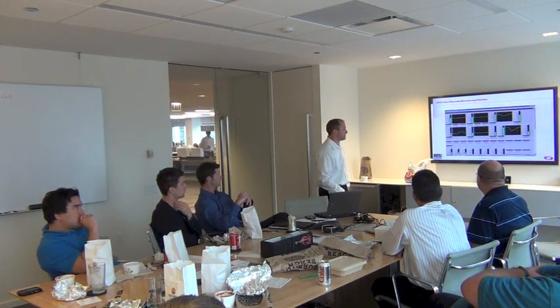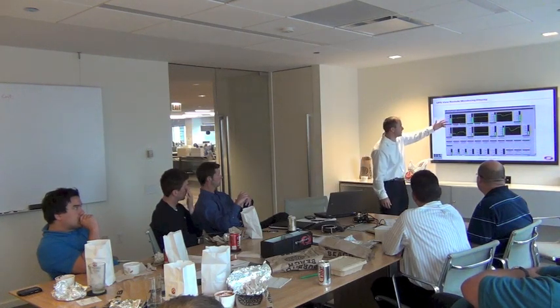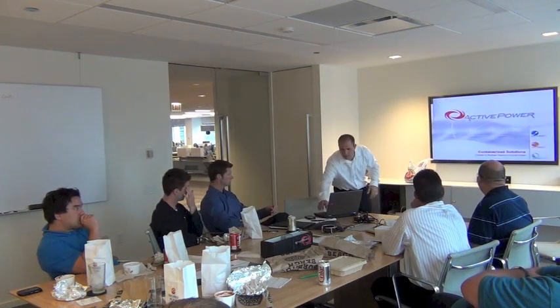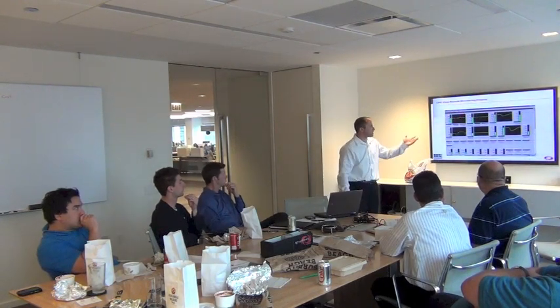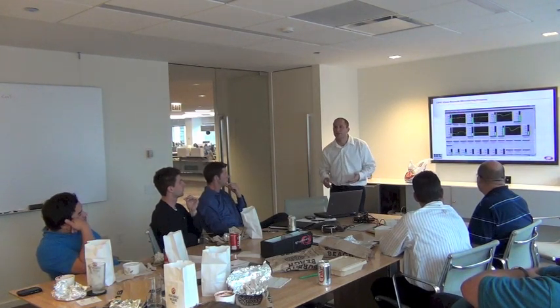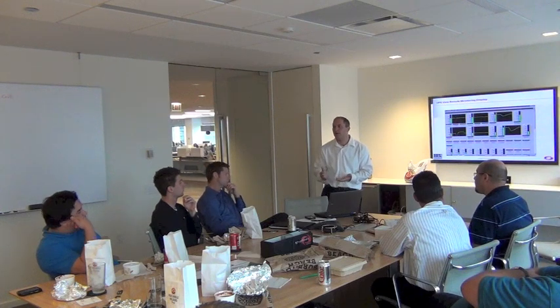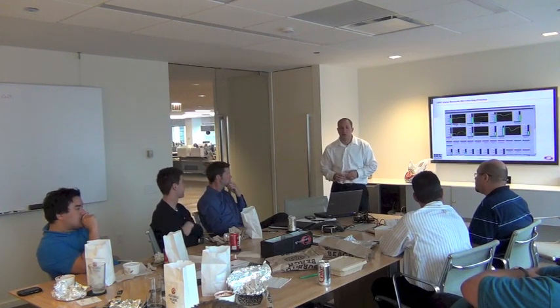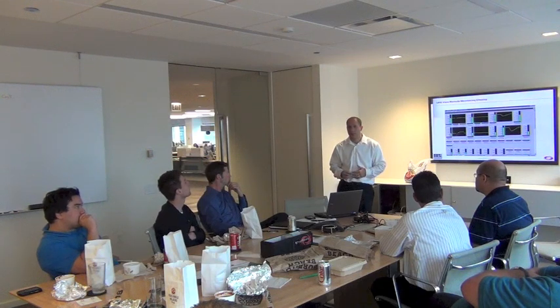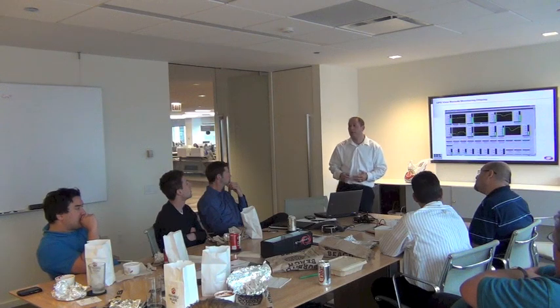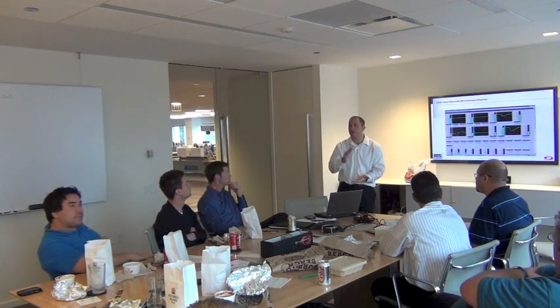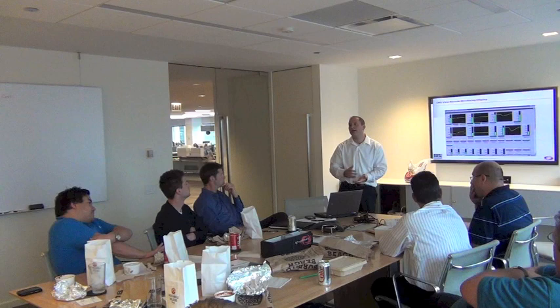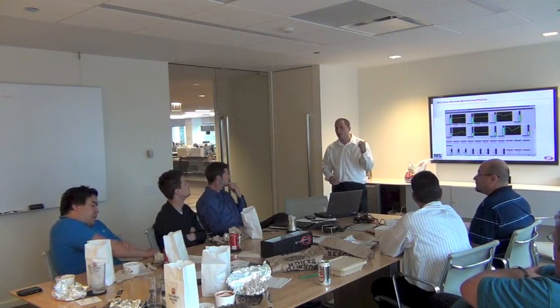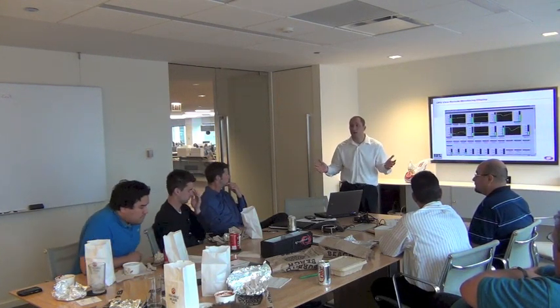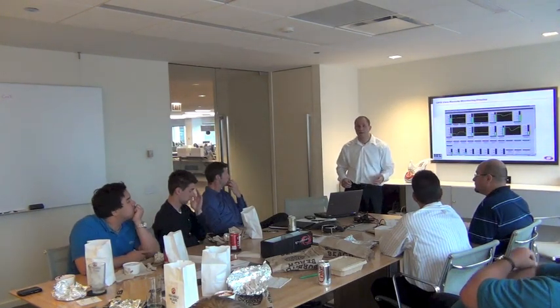This is just a snapshot of a typical setup for a customer. Maybe they want to see system input and system output voltage. One of the other nice things about it is this is the same software that the techs actually use in the field. There are different level passwords, obviously, to access different data. But it's a really nice feature, especially during commissioning. We were recently commissioning a pretty big job out west, and it really gives us a lot of visibility into what's going on when we have an outage, when the generator comes up to speed, how fast we're synchronizing, how fast we're locking on the load. We can download high-speed data capture plots. We can see exactly what's going on with the generator. Hey, your generator's overshooting. You need to dial down your ramp rate.